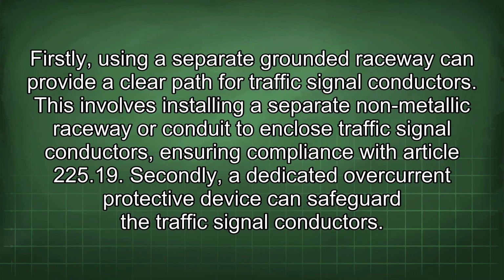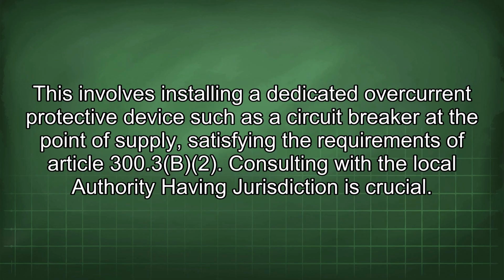Firstly, using a separate grounded raceway can provide a clear path for traffic signal conductors. This involves installing a separate non-metallic raceway or conduit to enclose traffic signal conductors, ensuring compliance with Article 225.19. Secondly, a dedicated overcurrent protective device can safeguard the traffic signal conductors. This involves installing a dedicated overcurrent protective device such as a circuit breaker at the point of supply, satisfying the requirements of Article 300.3b2. Consulting with the local authority having jurisdiction is crucial.